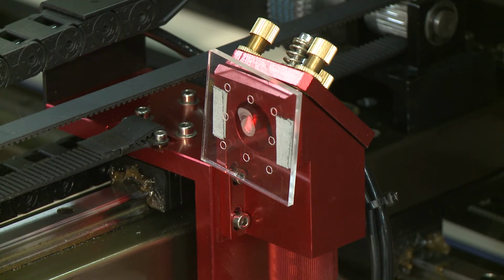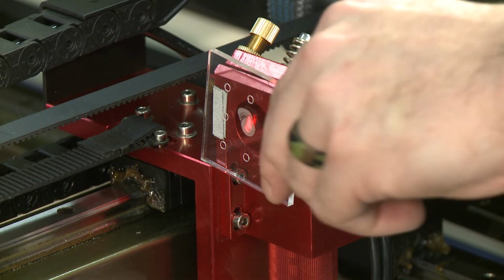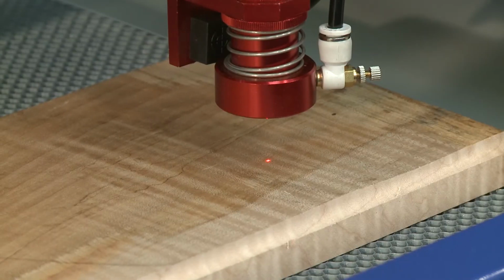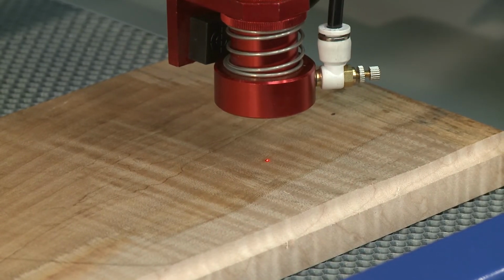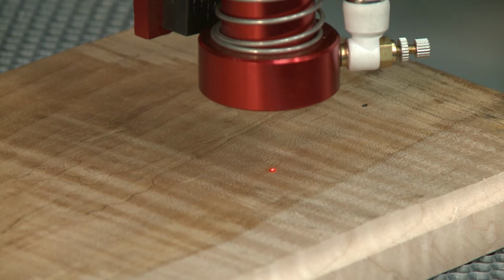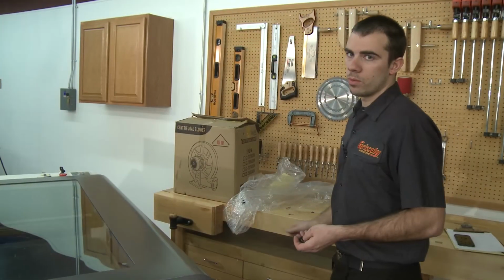Now that our reference laser is lined up on the center of the laser head, we can remove our Lexan. Now that the reference laser is lined up with the center of the laser head, we can use it as a reference on our workpiece. You can see that the dot made by the main laser and the reference laser line up in the same spot. At this point, we're ready to hook up the rest of the accessories, mostly being the air pump and the exhaust fan.